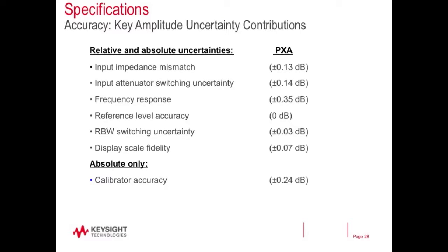And here's a slide that talks about all the different mismatches. Again, on the input impedance mismatch, if you use a little more attenuation on the input attenuator, you can improve that. I'll just leave it at that.